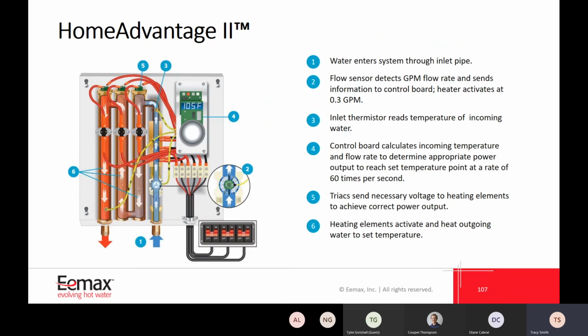And here's how it works. Water comes in through the inlet pipe, and the flow sensor determines the flow rate. The Home Advantage 2 units activate at 0.3 GPM. We read the temperature of the water, and the flow and the control board calculates how many kilowatts of heating power are needed instantaneously using the inlet water temperature, the gallons per minute flow rate, and the desired outlet temperature, and turns on the heating elements to deliver the exact amount of heating power needed at that specific time. When the demand goes away, the water gets turned off, so does the heating power.